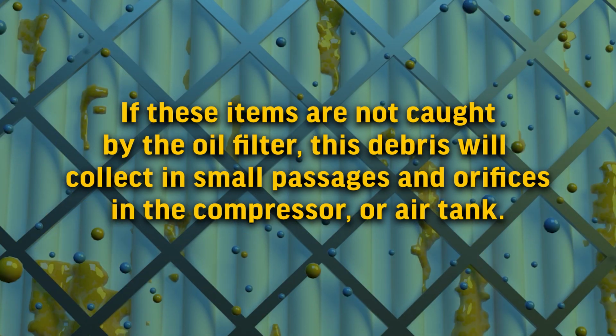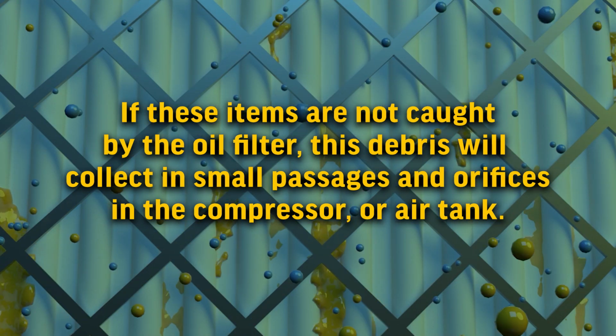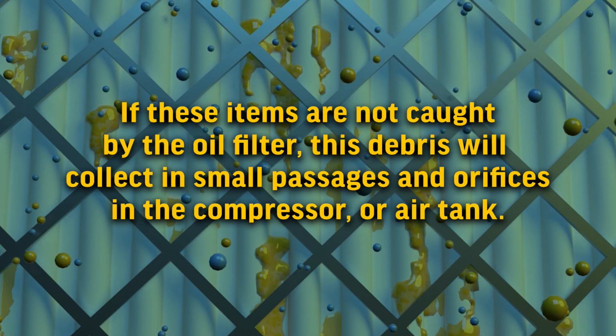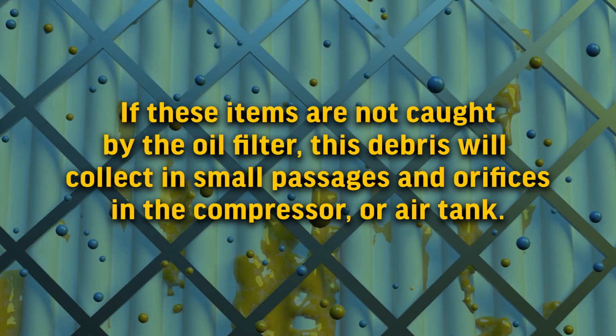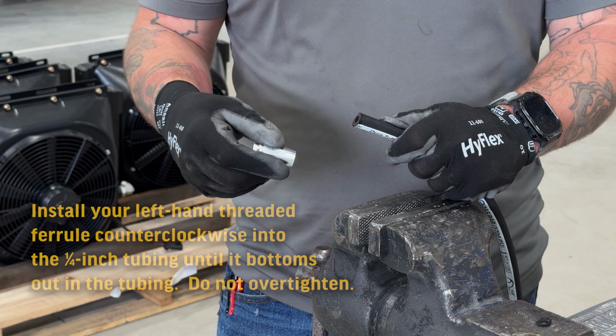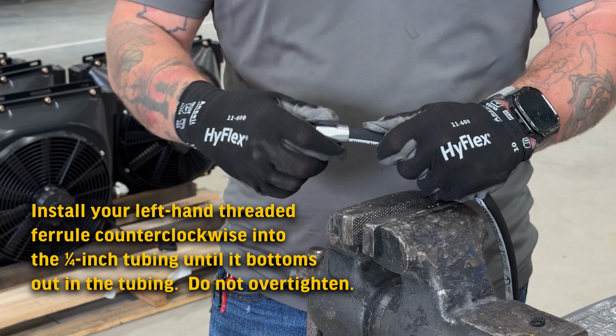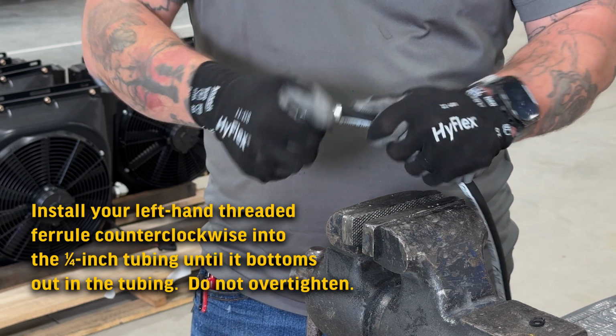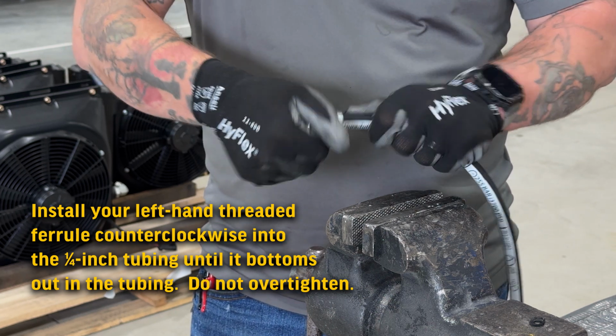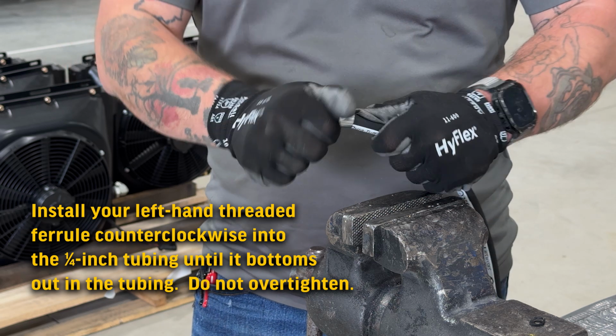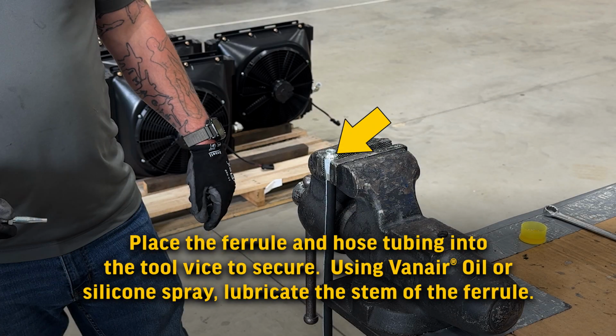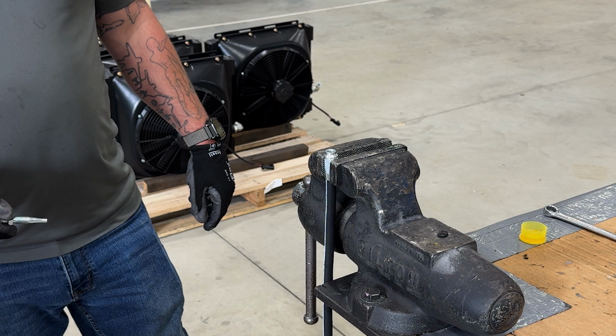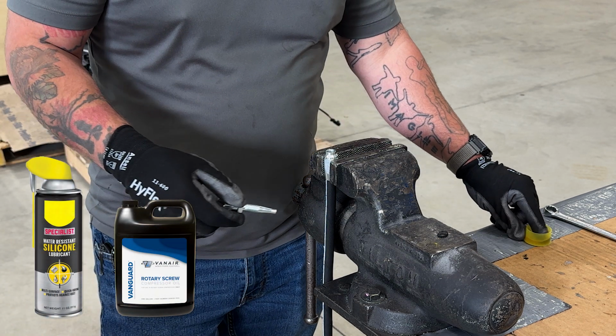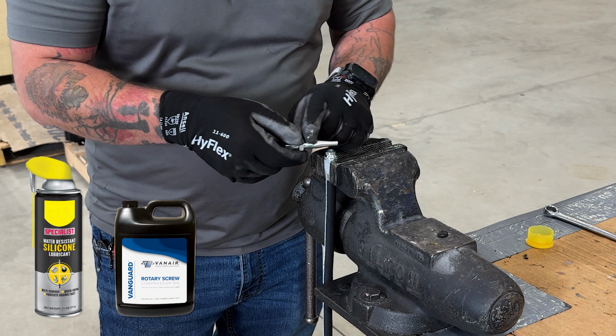If these items are not caught by the oil filter, this debris will collect in small passages and orifices in the compressor or air tank. Install your left-hand threaded ferrule counterclockwise into the 1/4 inch tubing until it bottoms out in the tubing. Do not over-tighten. Place the ferrule and hose tubing into the tool vise to secure. Using Vanair oil or silicone spray, lubricate the stem of the ferrule.